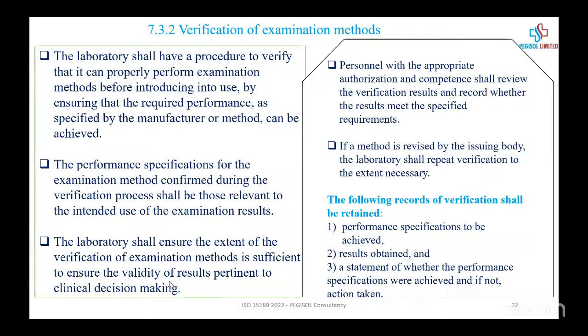the validity of results pertinent to clinical decision making. Then 4, personnel with the appropriate authorization and competence shall review the verification results and record whether the results meet the specified requirements. 5, if a method is revised by the issuing body, the laboratory shall repeat verification to the extent necessary.